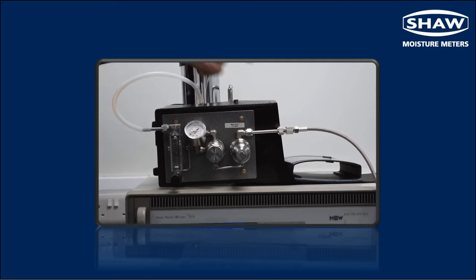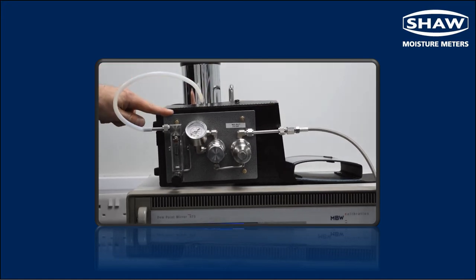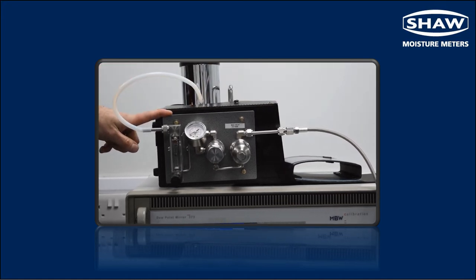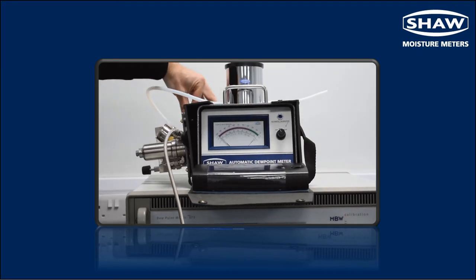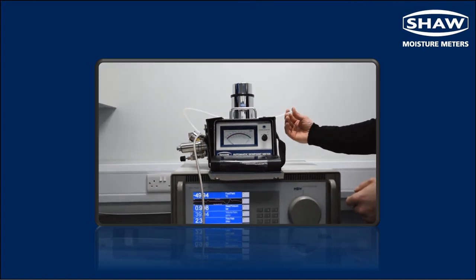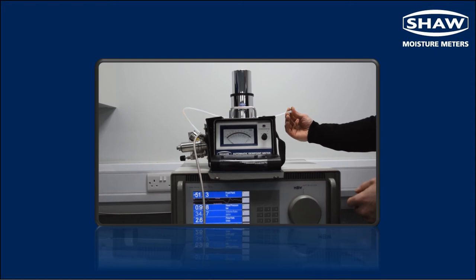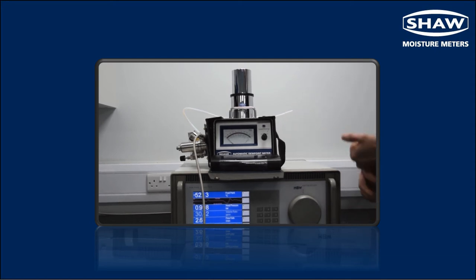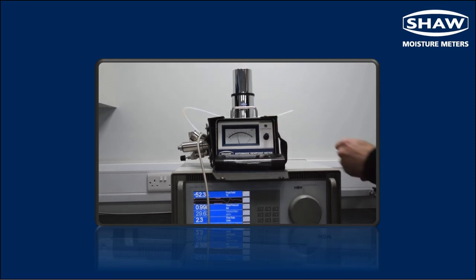So once we're happy that the sample line has been purged and the SU3 sample system has been purged, then we can expose the sensor to the process gas by raising the dry down head. And that's done by covering the outlet and allowing the pressure in the system to raise the head. And at that point we can start to take readings.